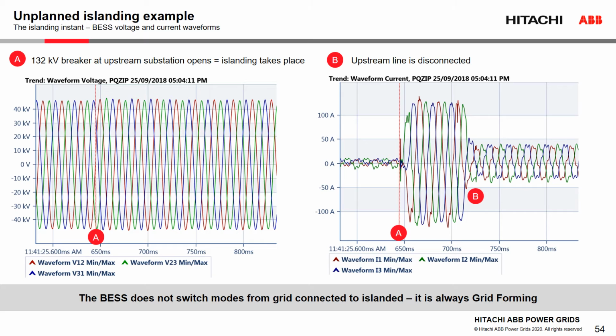And then on the right, we can see initially to point A, there is just a small current contribution, and this is in fact the voltage source converter syncing the harmonics on the NEM before the 132 kV incoming line opens. We can see that the grid-forming converter's current response is immediate because it is now the only voltage source in the grid, so the current supplied is load dependent. And then after about 70 milliseconds, the local substation protection opens and the current provided is just the local load requirements of the now independent grid.